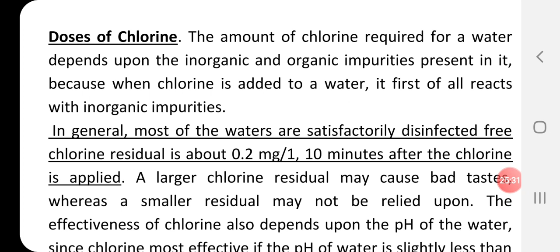In general, just go through the underlined portion of these notes. In general, most of the waters are satisfactorily disinfected when the free chlorine residual is about 0.2 milligram per liter. That means after adding the chlorine, and after killing the available bacteria, and after utilization by the inorganic and organic matter, the residual chlorine should be 0.2 milligram per liter. That means after utilization of all these things present in the water, there must be free or residual chlorine of 0.2 milligram per liter. Do you understand?